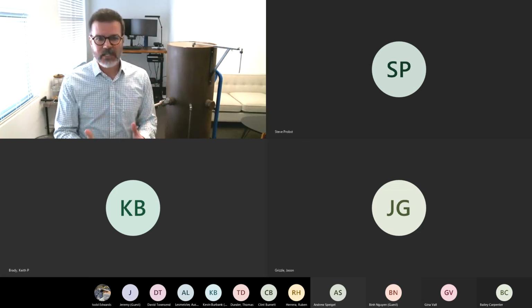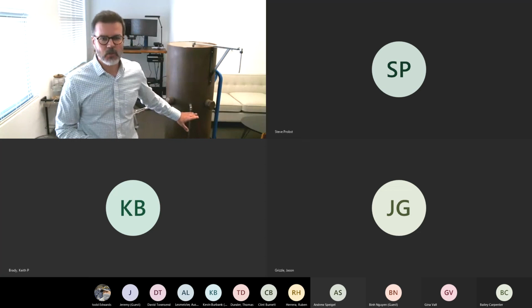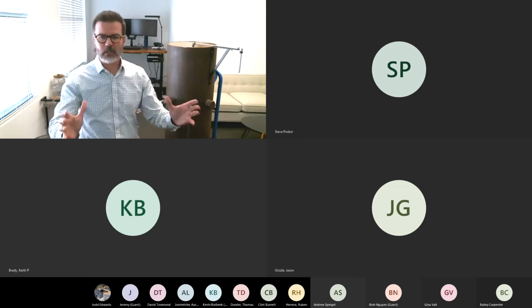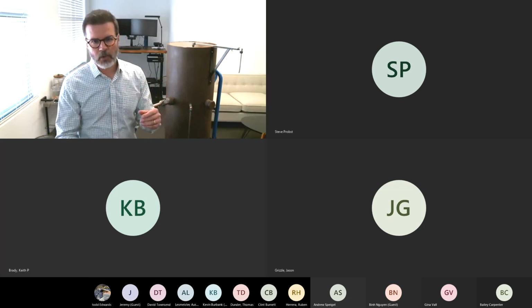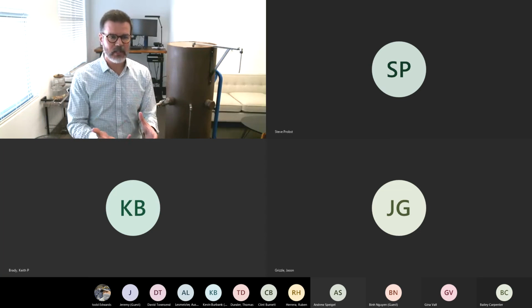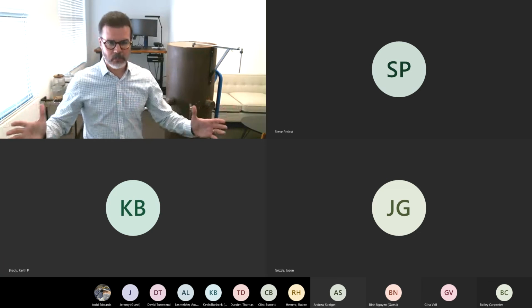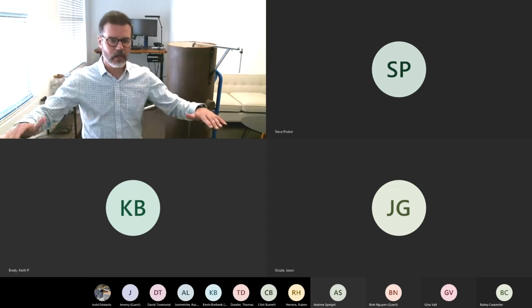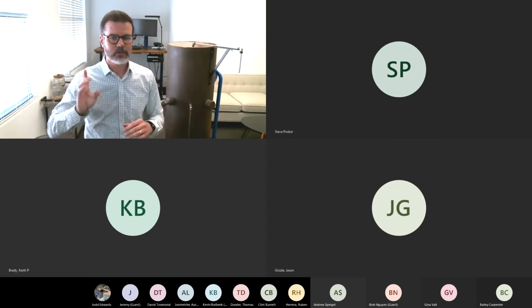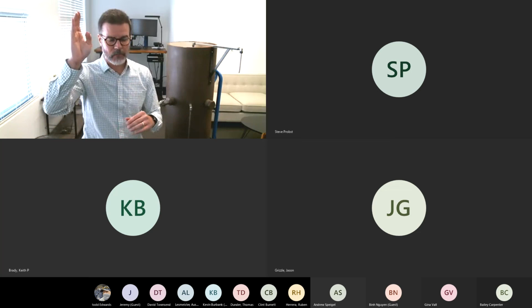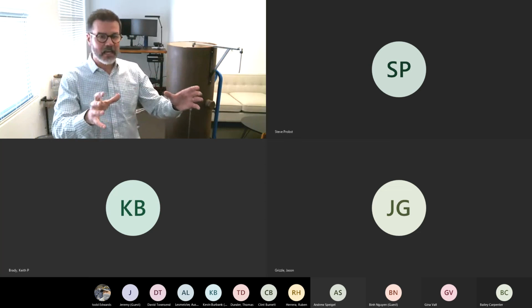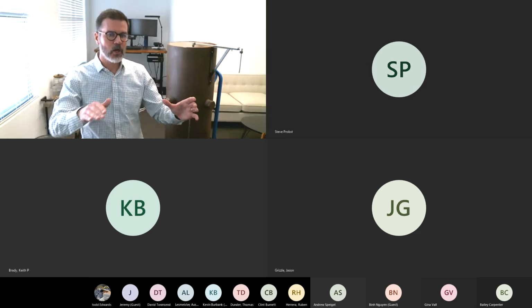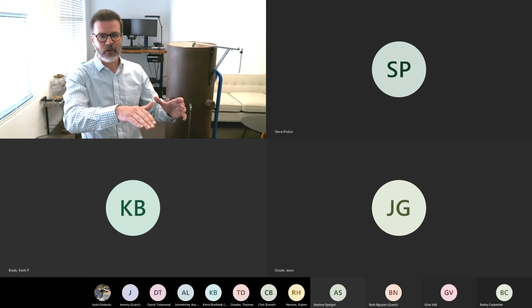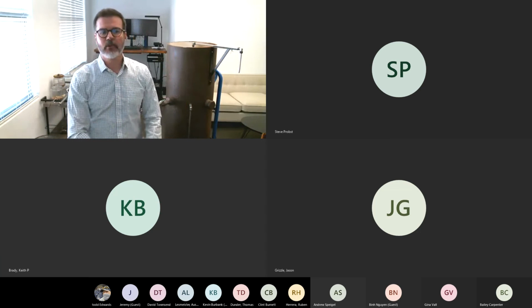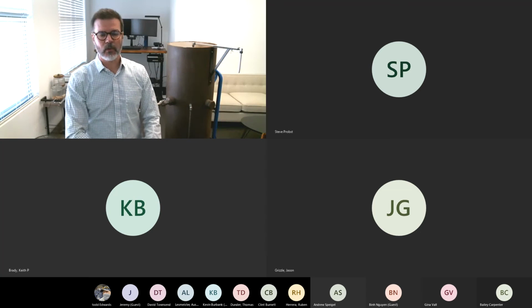If you're using an FTIR analyzer and you tap into a drop-down line like this, you can absolutely see when that moisture droplet hits the gas cell within the FTIR. You lose complete signal. None of your analytes are going to register at that point. You'll see a massive spike in moisture. And if you do happen to get a reading, you can look at your NO2 and you can see that it completely drops out of the sample.